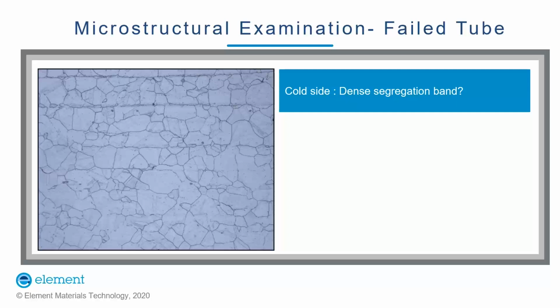Detailed microstructural analysis was done on this failed tube. Analysis was done both at the hot side, where a crack was observed, and at the cold side, where no failure or crack was observed. A detailed microstructural comparison was done for these two locations and is presented in this slide. The microstructure at the cold side showed segregation bands of precipitate, as you can see in the micrograph. As per the supplied information, the cold side temperature is supposed to be below 100 degrees centigrade. Therefore, it can be confirmed that this segregation band formed during the manufacturing process of the tube.